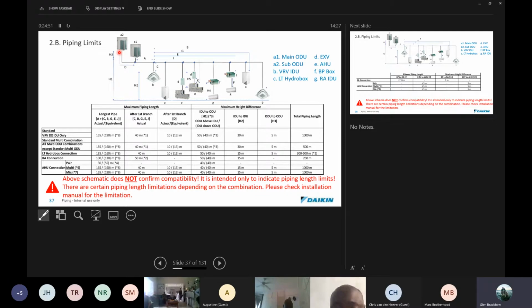Now we talk about 2 types of piping lengths here: the actual, which is what you measure with a tape measure, and the equivalent piping length. Equivalent piping length is what we add up for each elbow or each fitting, and what that adds to the system. Now, if you think about a 3/8" elbow, if you take it as a straight piece of piping, it is almost equivalent to 300 millimeters of piping. So although that little 3/8" elbow you can hold in your hand, its actual straight length of piping is quite a bit longer than it looks. So we need to consider that, because that is what equivalent piping is.